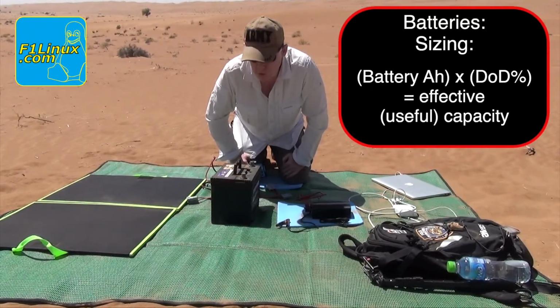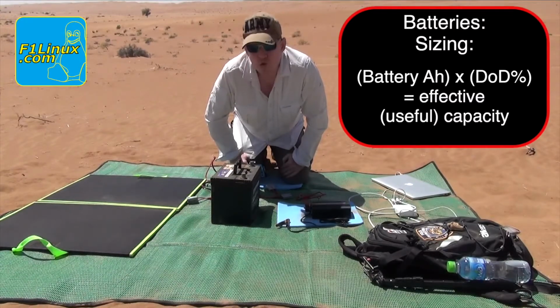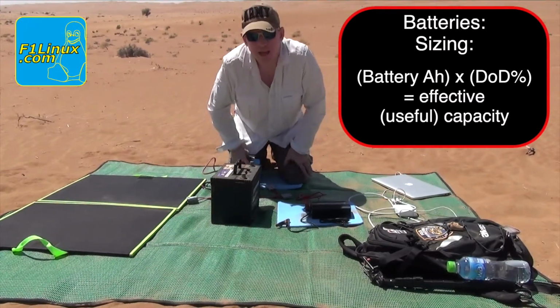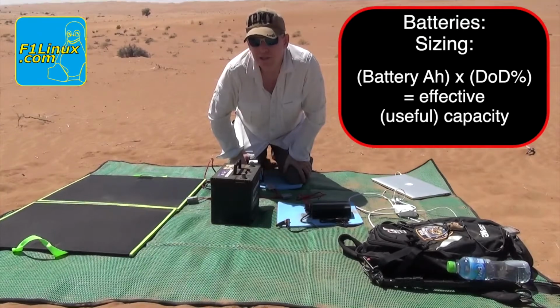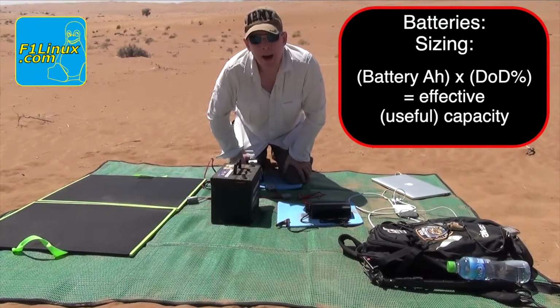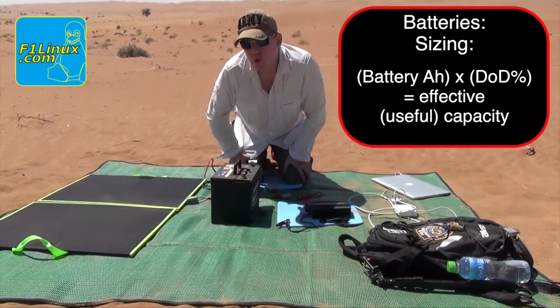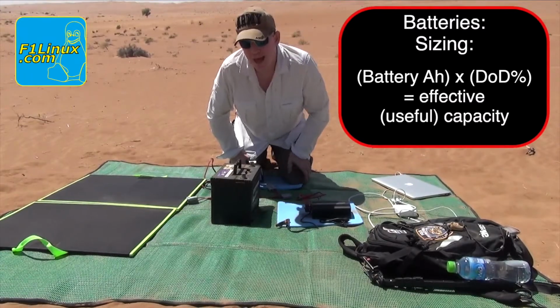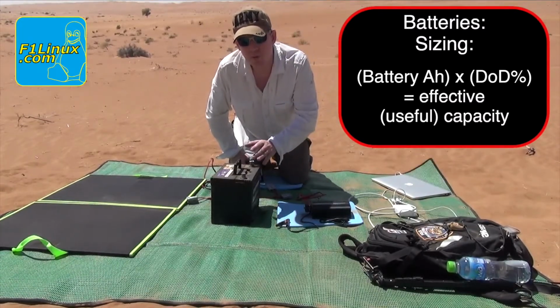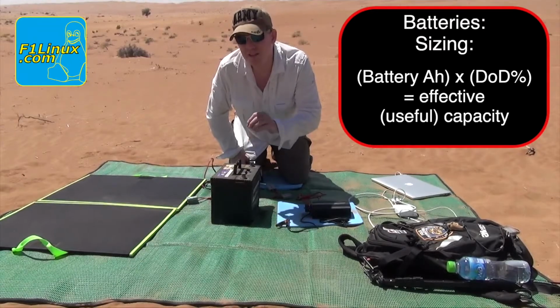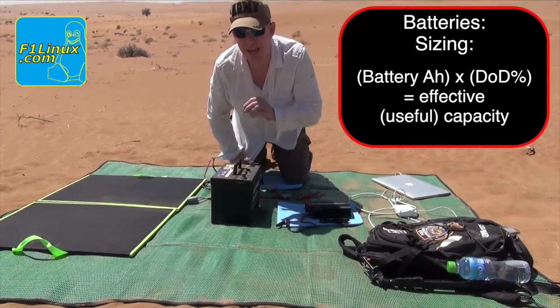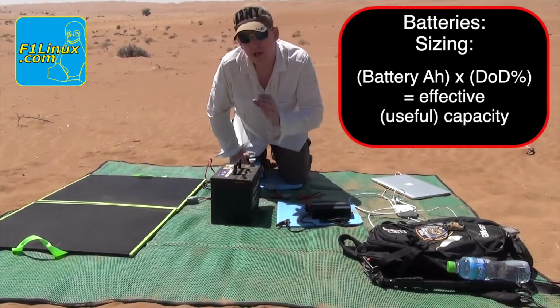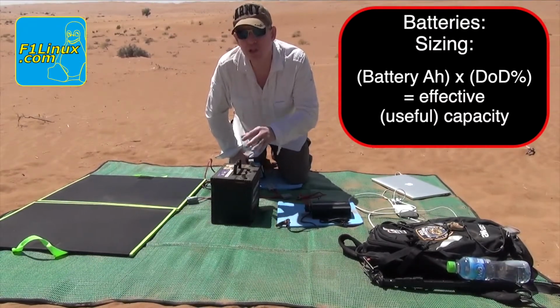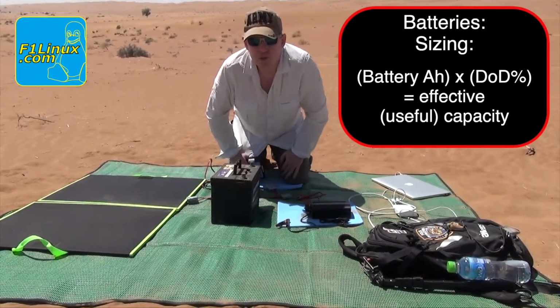If you were to get what's called a cranking battery, the standard battery you see in cars, its depth of discharge is only 10%. So that 100 amp hours is effectively only 10 amp hours. Cranking batteries are not really suitable for solar power systems.